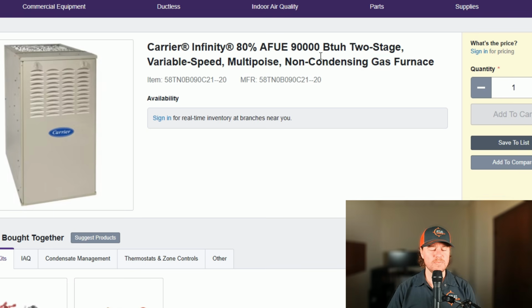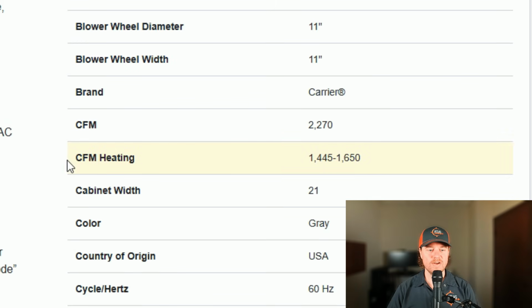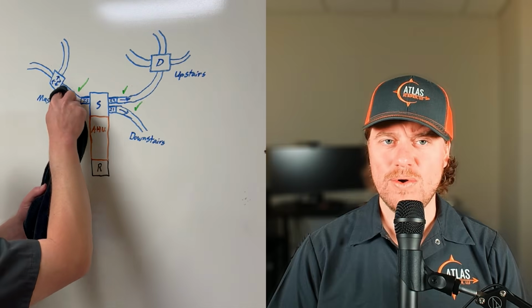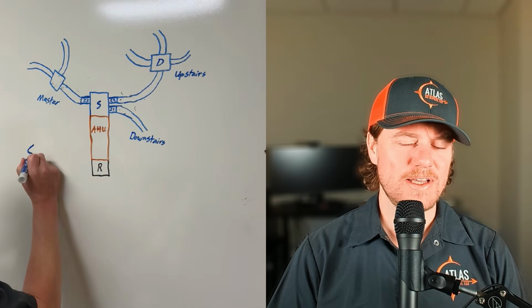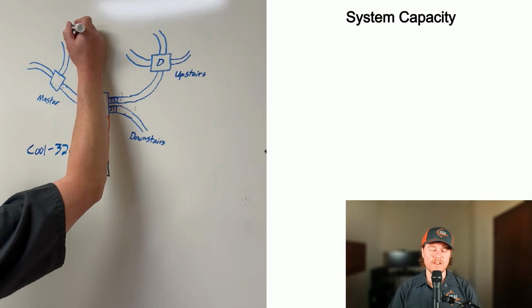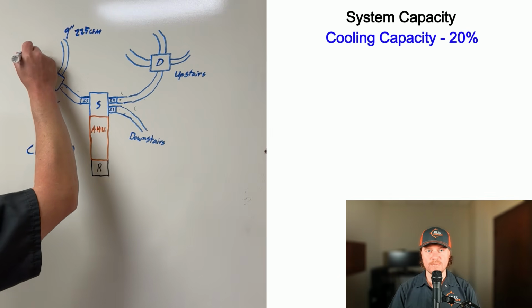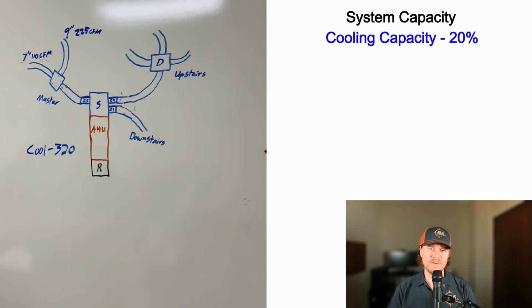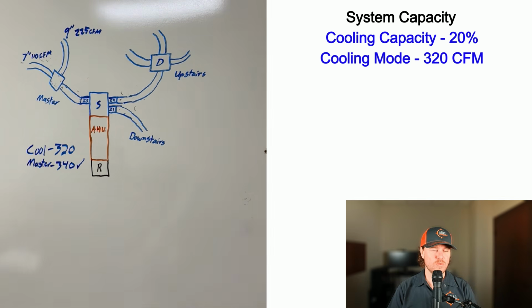And if we take a look at the minimum airflow requirements in heating mode, let's scroll down here. Right here, we can take a look at heating CFM, and you can see that it ranges from 1,445 CFM to 1,650 CFM. Basically, in first stage, we're going to be running roughly 3.5 tons of airflow. Now, what would happen if I designed out a zoning setup for cooling mode? The lowest operating capacity would be in between 20 to 25%. On a 4-ton system, that would be a little over 300 CFM or pretty close to 1 ton of airflow.